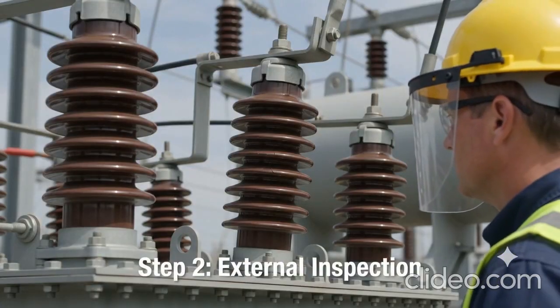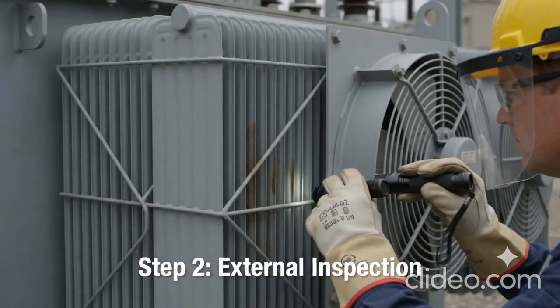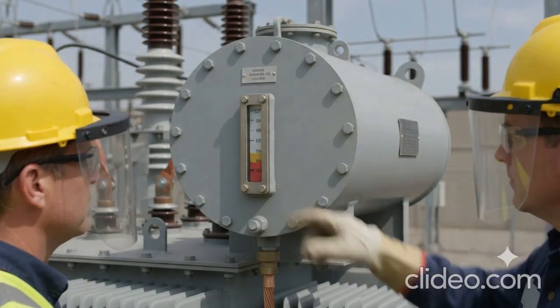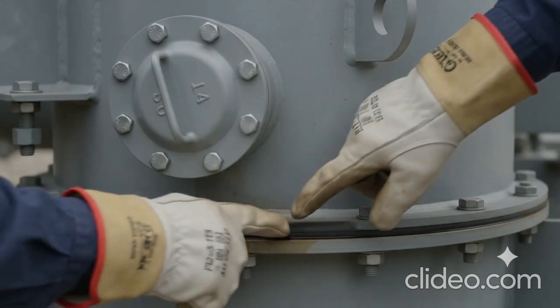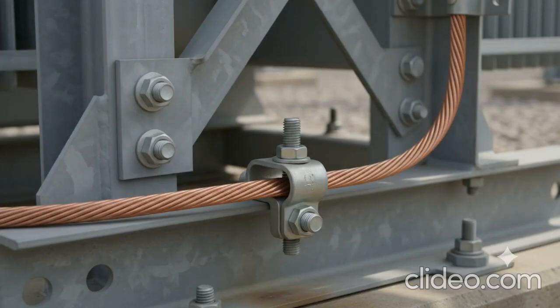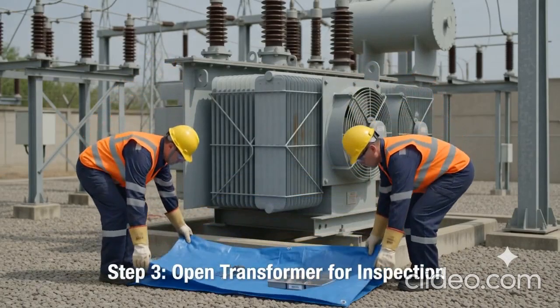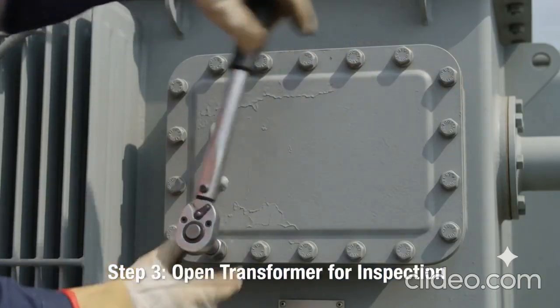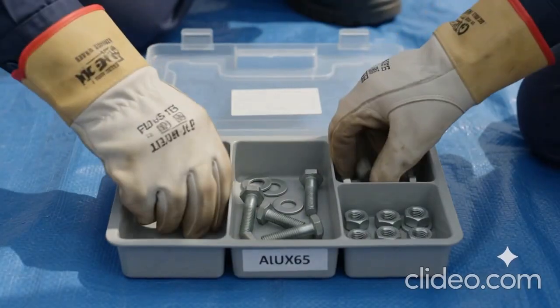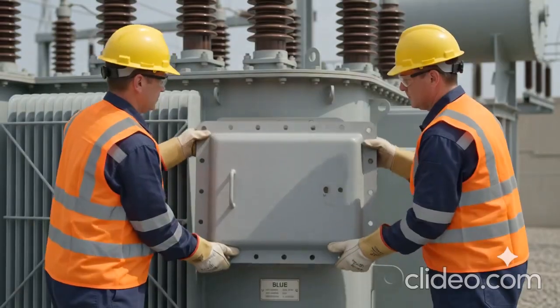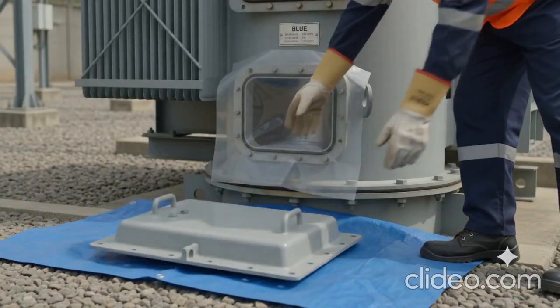The external condition of the transformer is inspected carefully. Technicians check for oil leakage, damaged bushings, loose connections, and corrosion. They also check for abnormal oil levels. Once the external inspection is complete, the required inspection covers are opened. Cleanliness is important because moisture and dust must not enter.